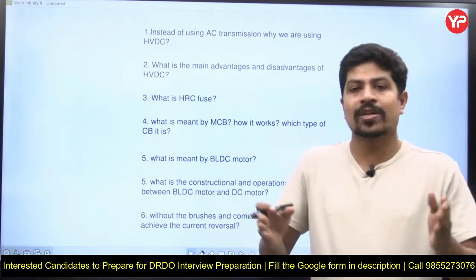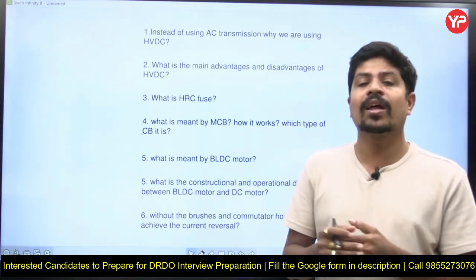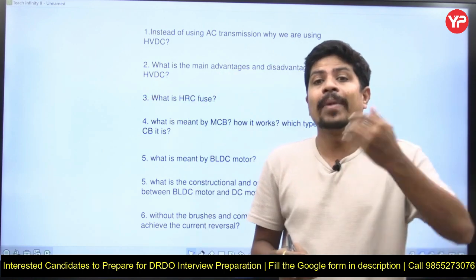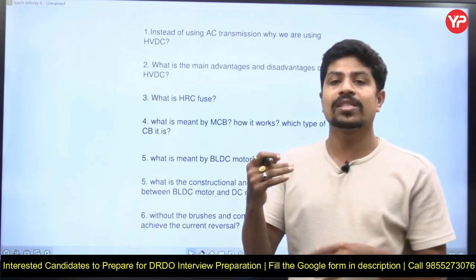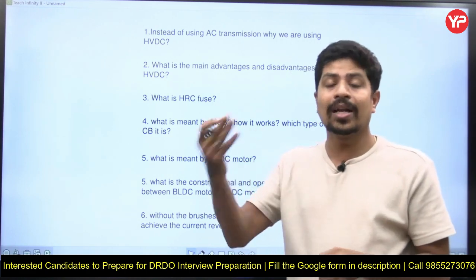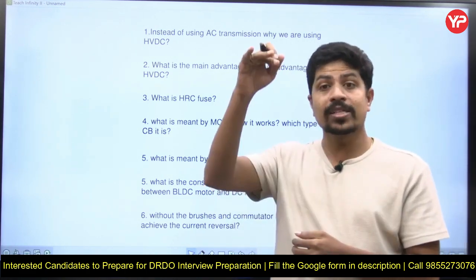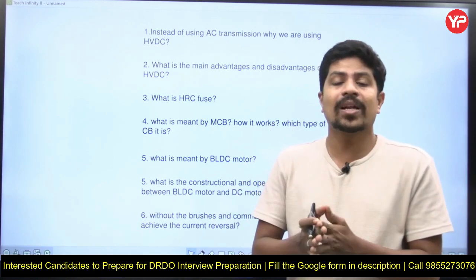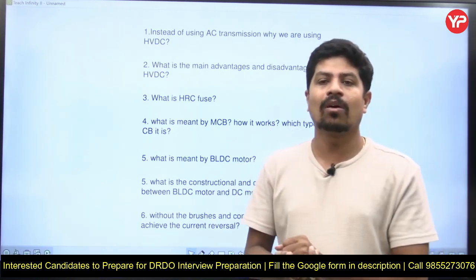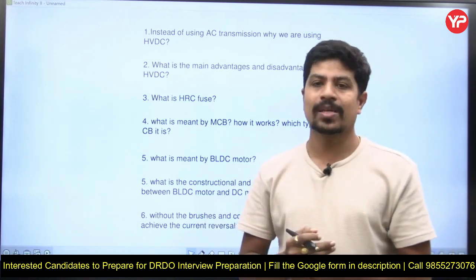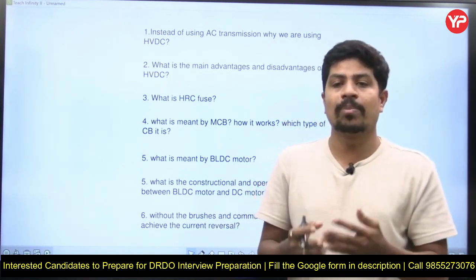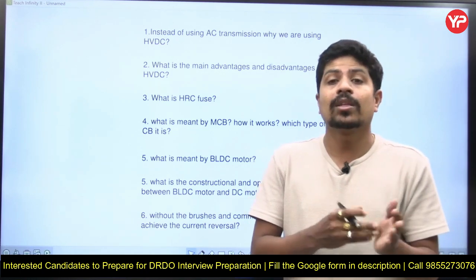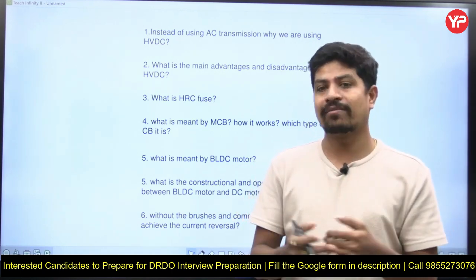The main reason to go for HVDC is power system stability. With AC power transmission, as the length of the transmission increases, the reactance increases and maximum power transfer capability decreases. Therefore, the load angle delta must increase to send the same amount of power, decreasing stability. There is a relationship between load angle delta and stability — delta should be less than 90 degrees for the system to be stable. The main reason for choosing HVDC over HVAC is to have very good power system stability.